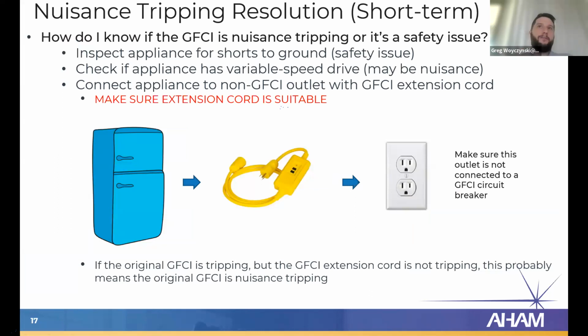How do I know if the GFCI is nuisance tripping or it's a safety issue? So you can do your normal inspection of an appliance for shorts to ground. So if you see things like nicks in the wiring, nicks in the coating, motor windings, pitting, or of course any arcing, those could be indications of shorts to ground, and that's a safety issue. So of course, something's wrong with the appliance there. The GFCI is just doing its job. It's not nuisance tripping in that case.